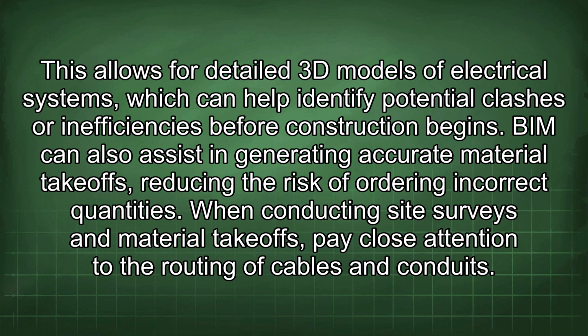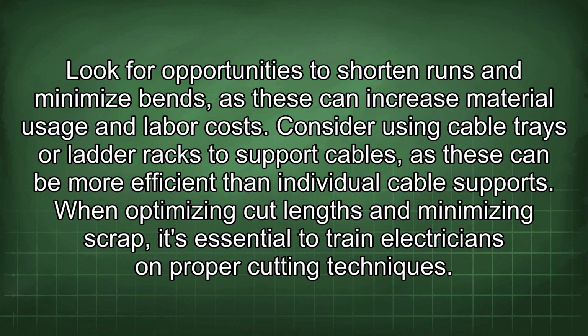When conducting site surveys and material takeoffs, pay close attention to the routing of cables and conduits. Look for opportunities to shorten runs and minimize bends, as these can increase material usage and labor costs. Consider using cable trays or ladder racks to support cables, as these can be more efficient than individual cable supports.